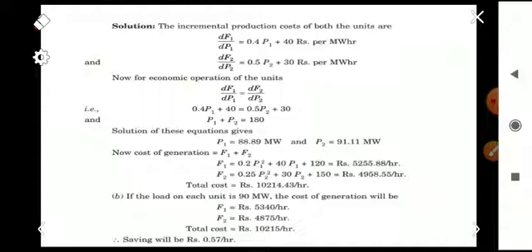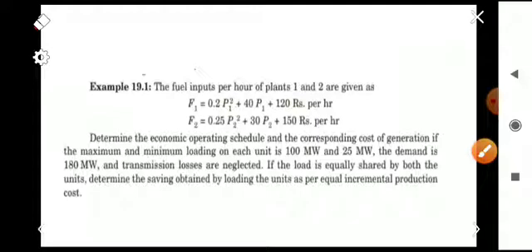For economic operation, the incremental production cost dF1/dP1 should equal dF2/dP2. Substituting: 0.4P1 + 40 = 0.5P2 + 30. This is equation number one. The second equation from the power balance is P1 + P2 = 180 MW, the total demand. We now have two equations with P1 and P2 as unknowns.